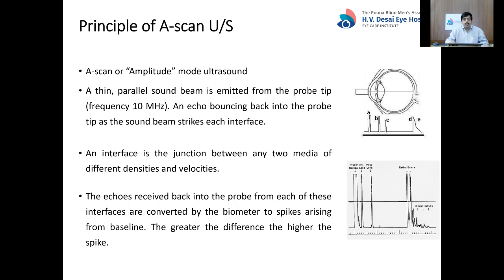It is called A-scan because it is an amplitude mode of ultrasound. A thin parallel sound beam is emitted from the probe tip, usually at a frequency of 10 to 12 megahertz. The sound beam bounces back into the probe from the interfaces. An interface is a junction between any two media of different densities and velocities.